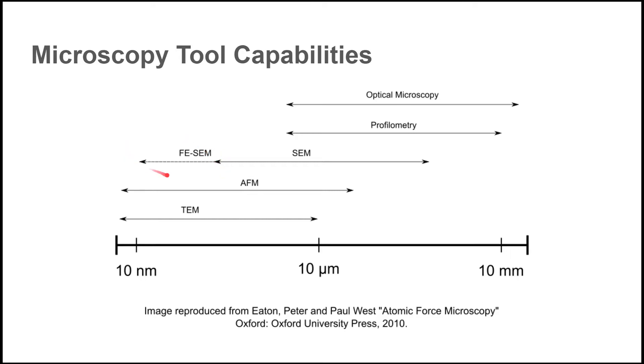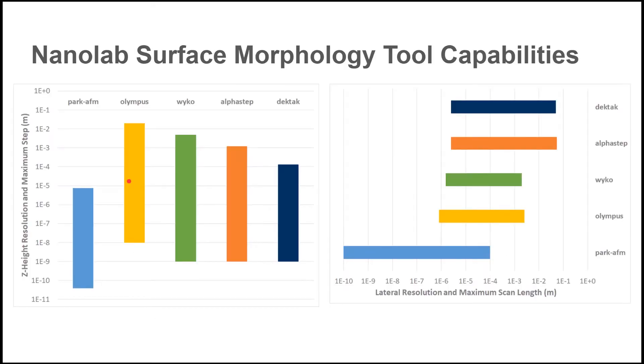Nanolab's SEMs are both field emission SEMs. The lateral resolution of an AFM depends on the probe chosen for the measurement, but can be as small as a few nanometers. Z resolution is measured in picometers. The only technique with consistently higher resolution than AFM is TEM. The trade-off with this high resolution is a limitation on the maximum scale of the measurement. The Park AFM cannot measure a step taller than 7.5 microns, and the imageable area is only 100 by 100 microns square.